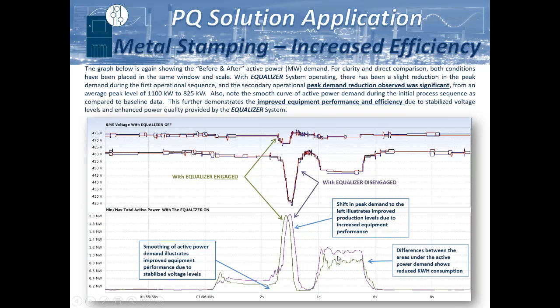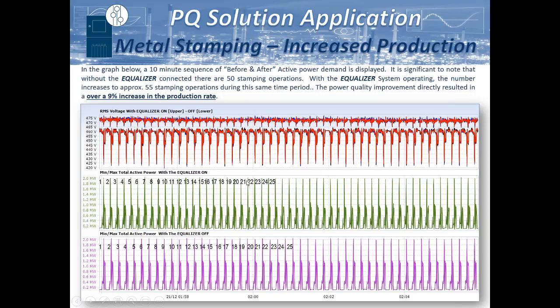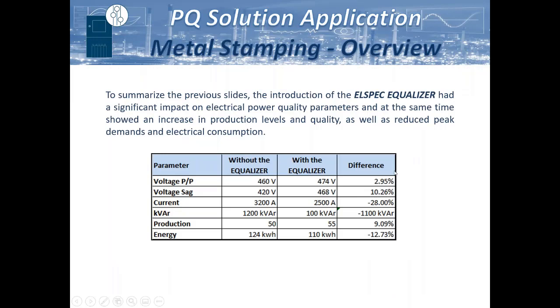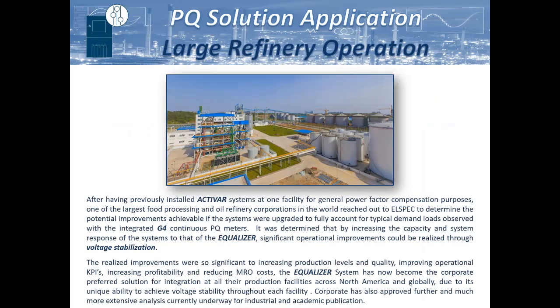And you can also see here that the difference in the areas underneath these curves is your kWh savings. So you can see the process improvement, and it increased their production rate. In this chart, it's very easy to see the time required to do 25 stamps versus 25 stamps with the system off; we increased their production rate by a little over 9%. Quite significant results. The peak current dropped by 28%, the production improved by about 9%, all while the energy consumption was reduced by over 12%. So some very good impacts on this.